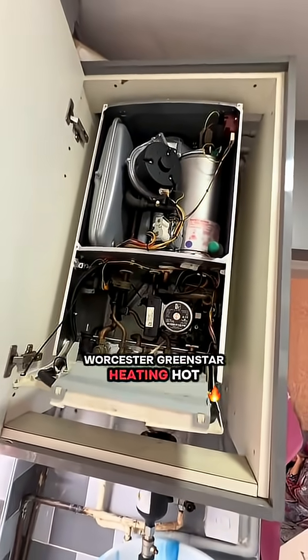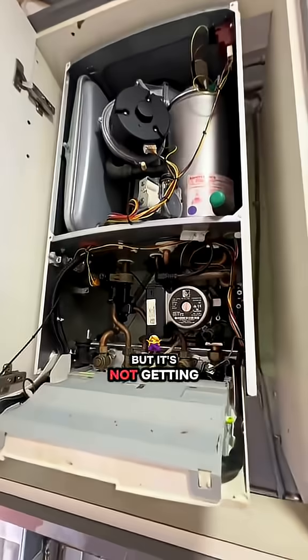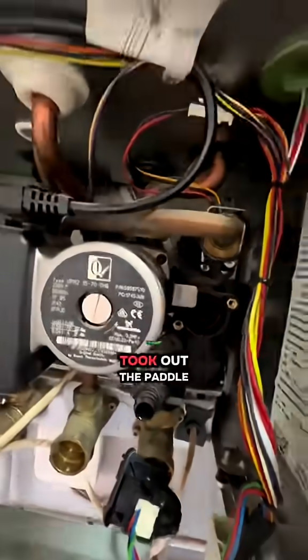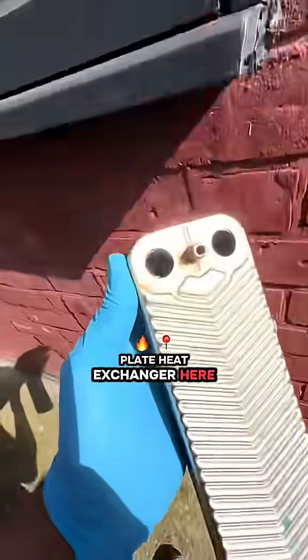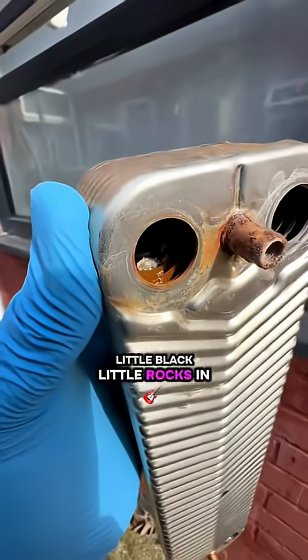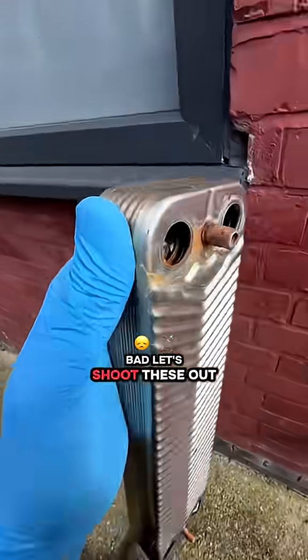The Greenstar was heating hot water but it was going hot and then cold, not getting really hot. Stripped it down, took out the paddle, and had a look at the plate heat exchanger. Look at that — you can see the little black rocks in there. Bad. Let's shoot these out.